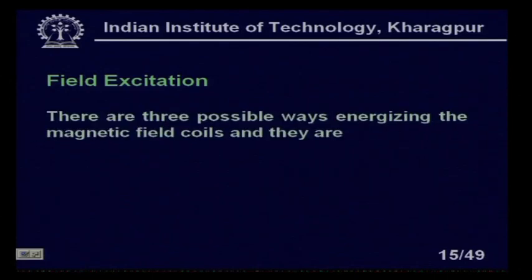For field excitation of the electromagnetic flow meter, there are three possible ways to energize the magnetic field coils: DC, 50 Hz AC, or pulsating/interrupted DC. When DC is applied, the fluid moving in the DC magnetic field generates a voltage via Faraday's law. AC at 50 Hz has been used for many years and allows easy signal amplification. Pulsating DC is the most modern method.